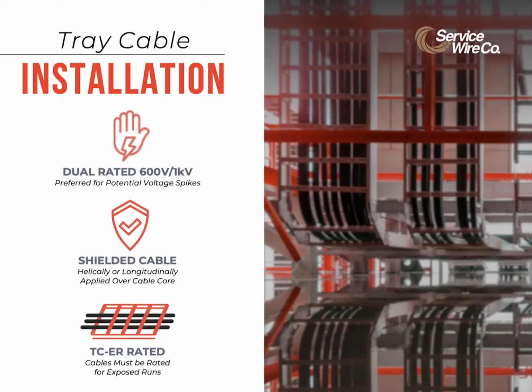Additionally, dual-rated tray cable has a smaller outside diameter than traditional 1 kV tray cables, making it preferable in space-constrained installations. Service Wire's tray cable is suitable for installations in cable trays supported by messenger wire in open air raceways, channels, conduit, and ducts. It is also TCER rated per the National Electric Code.